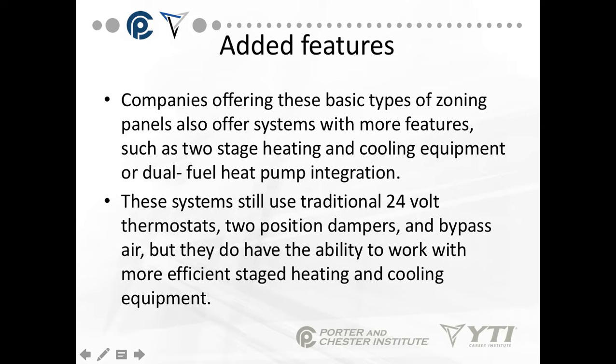Companies offering these basic types of zoning panels also offer systems with more features, such as two-stage heating and cooling and dual-fuel heat pump integration. These systems still use traditional 24-volt thermostats and two-position dampers and bypass air, but they have the ability to work with more efficient staged heating and cooling equipment.